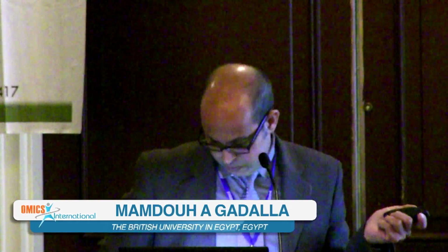by moving these exchangers. Now look at the new network. There is no more exchanger within this area except this small one. Exchanger 3 is here, 4 is here, and 5 is here. And this is the new exchanger unit, and this is the new exchanger unit. So look at the benefits. This is the optimum network produced, and these are the results of the case.